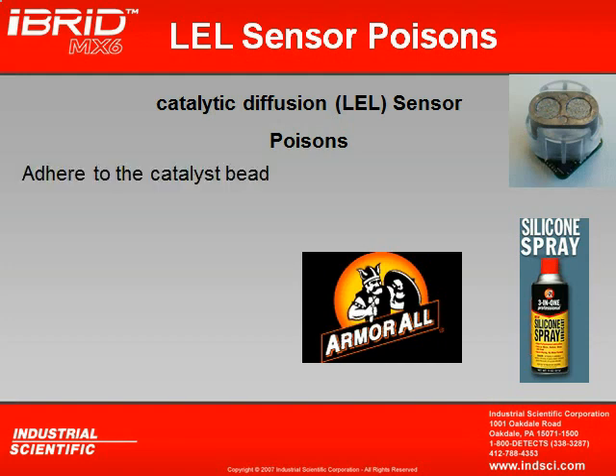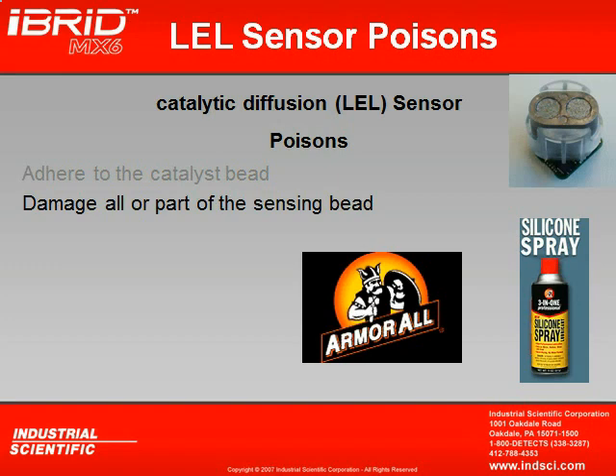What poisons do is they adhere themselves to the catalyst bead, and they can damage all or part of that sensing bead. Our biggest poison is silicone. Silicone can be found in many different products. It's in Armor All. There's other types of silicone greases, lubes, and caulking, where if the silicone is off-gassing, you have that hot burning bead. Silicone vapors may actually melt on the bead, coat the bead, and insulate the bead.